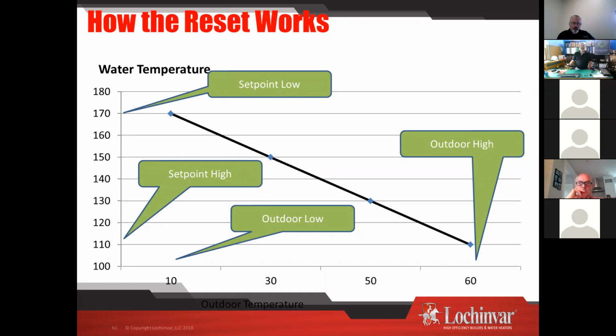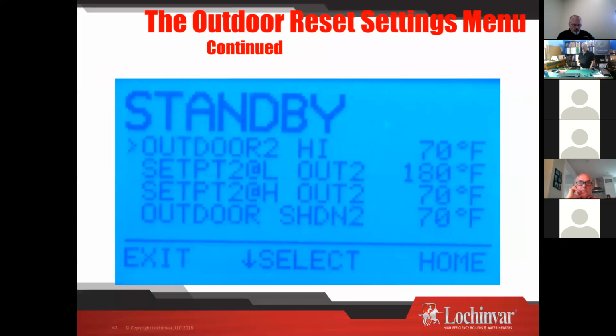It's like 80% of the time you need less than 50% of the BTUs. If you have baseboard, the way to get down to 50% of the BTUs on baseboard is 135 degree water. So you can kind of take a look at that curve and say, well, I bet you we spend a lot more time below 50 degrees where we could probably be closer to that 130. So definitely some things to look at in adjusting your outdoor reset curve. And this is just, you can set them all up 3 times.